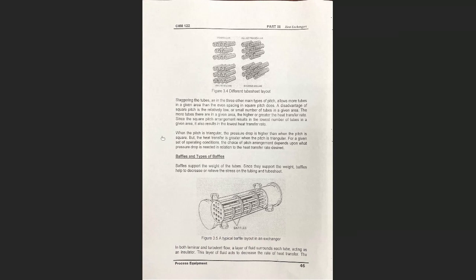هذه تعتبر مشكلة بالنسبة لك، يعني أنت زودت مساحة الهيت ترانسفير اريا، وبالتالي الهيت ترانسفير صار عندك أسرع، لكن عندك مشكلة إنه انخفاض الضغط بالنسبة للسائل الموجود يعتبر صار أعلى يا إخوان. جميل. وبالتالي ذكرنا مسألة البمبس هذه pumping requirement or compression requirement. Okay.